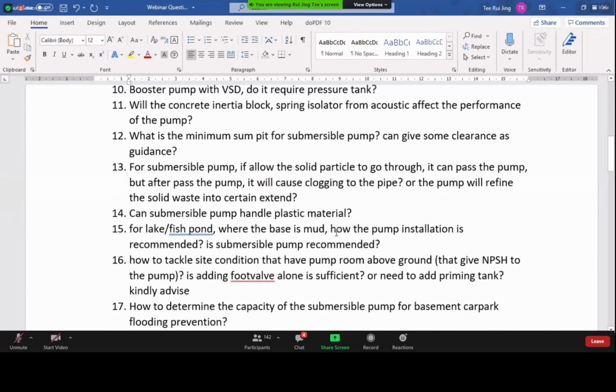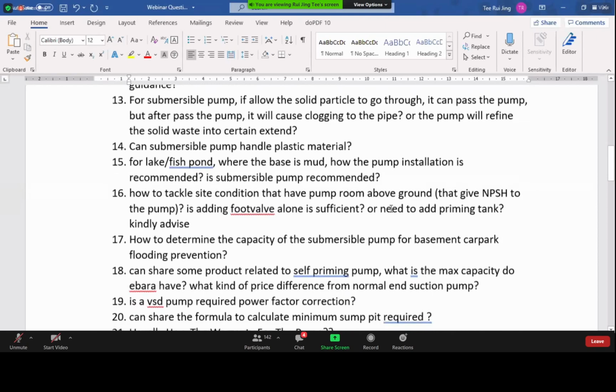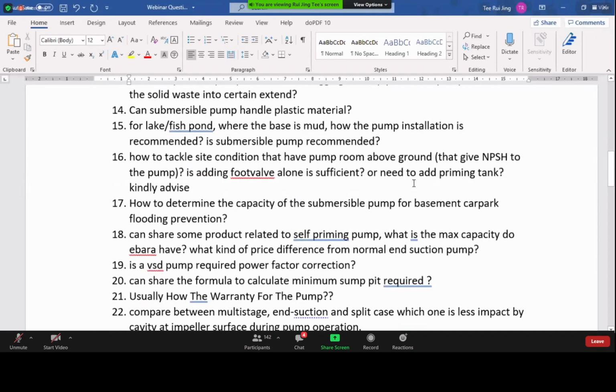So if your pump requires, for example, 4 meter NPSH, but you can only give 3 meters, by calculation, then that means the pump will have suction problems. So even if you put a pump on top, the pump will not be able to take suction.